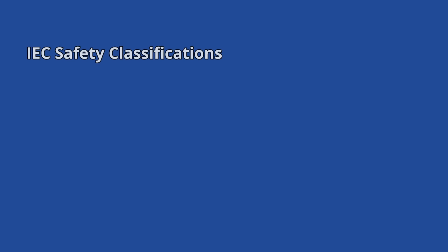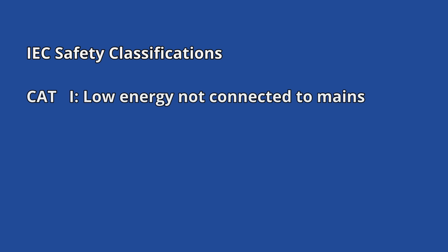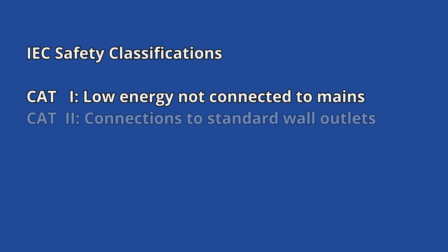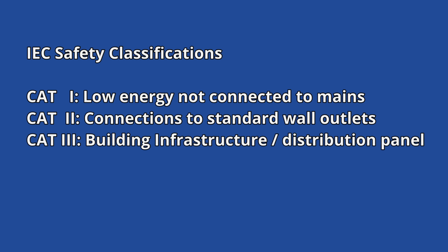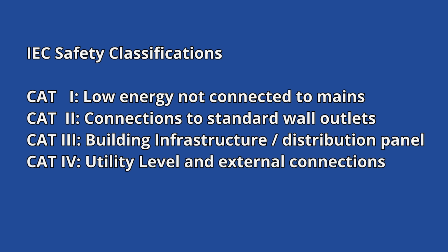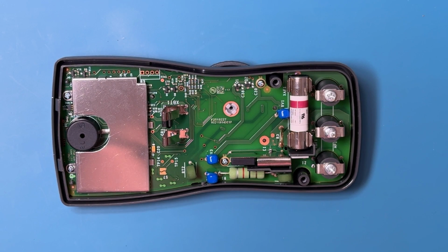The IEC has defined 4 safety categories for electrical test equipment. Cat 1 is the lowest category and refers to most electronic devices. Cat 2 is the most common household rating and would apply to most of the electrical outlets in a home. Cat 3 would be the environment of an electrical distribution panel, and Cat 4 refers to connections to the main electric utility and outdoor connections. When assessing safety, we need to consider safety to people and safety to our electronic test device.